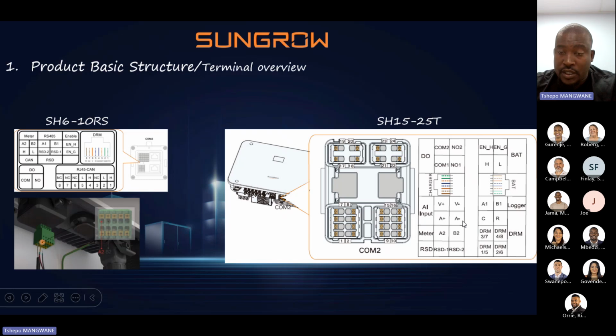What am I leaving out? Should the customer have a generator integration scenario, where they have a generator on the system, then he will use the DO. But we will be available for assistance online as well. We'll advise him where to connect, which is our COM2 and COM1, normally open 2 and normally open 1. This is where we do our comms from the generator side.